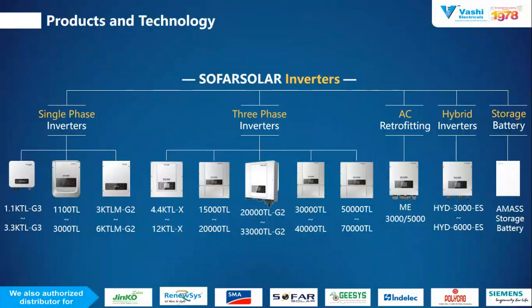The 50 to 70 kilowatt range of inverters is highly used for commercial and industrial purposes. These inverters all have 3 MPPT. In the 50 kilowatt, you can connect a total of 10 strings, and in the 60 to 70 kilowatt inverter, you can connect a total of 12 strings.